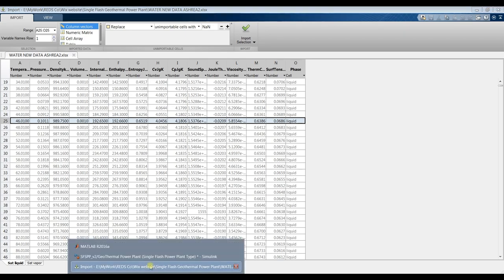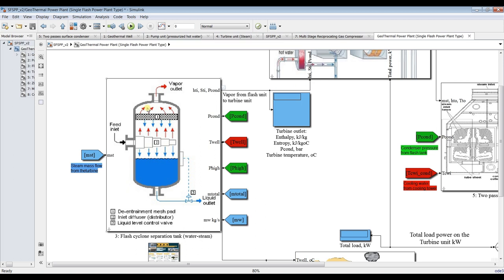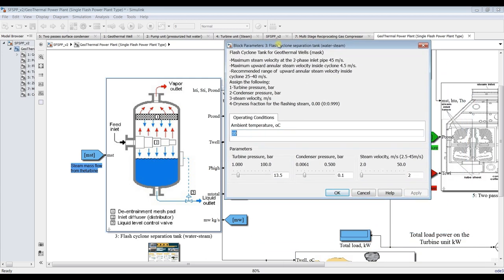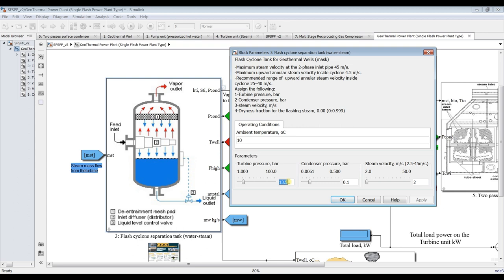Inside the flashing tank, double-click to control parameters. We can control pressure at zero time or in dynamic mode — if you set simulation time to infinity and move the slider, you can see effects immediately. Suppose I need 13.5 bars turbine pressure and 0.1 bar condenser pressure. Steam velocity is a parameter responsible for flashing tank dimensions: height, width, diameter of steam tube, and so on. Reference temperature is set to 10 degrees Celsius — quite normal for exergy analysis. It's expected to reach 190 degrees Celsius as the high temperature.